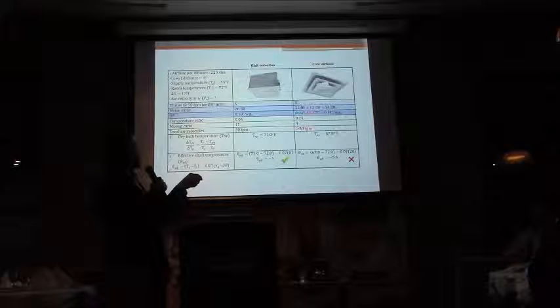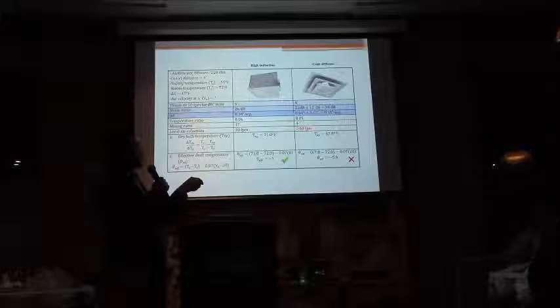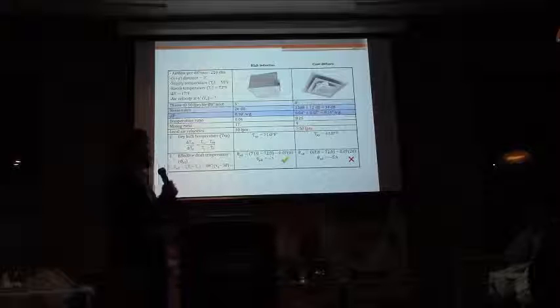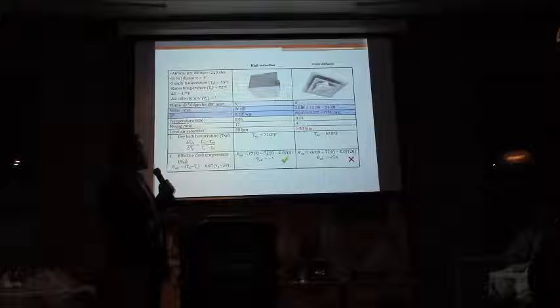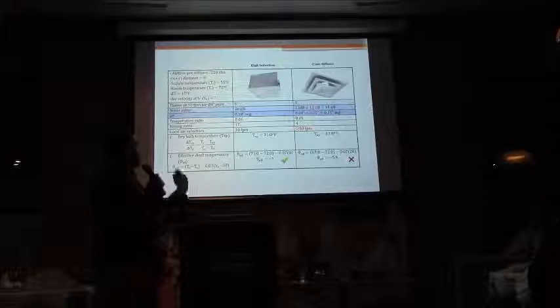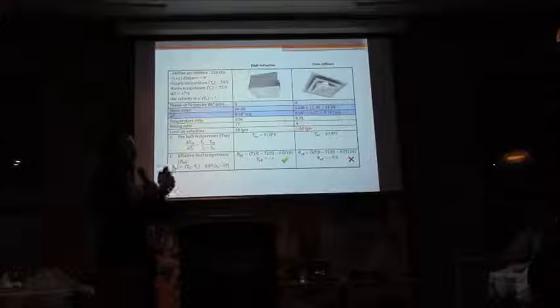And your static pressure losses, if you add 0.07 there, you're at 0.11. And your velocities, like I mentioned, are going to be much higher if you're in that zone where you're getting 80% of the air. So in reality, there is no trade-off to high induction. In reality, you have less noise, less static pressure loss, more comfort, and energy savings.